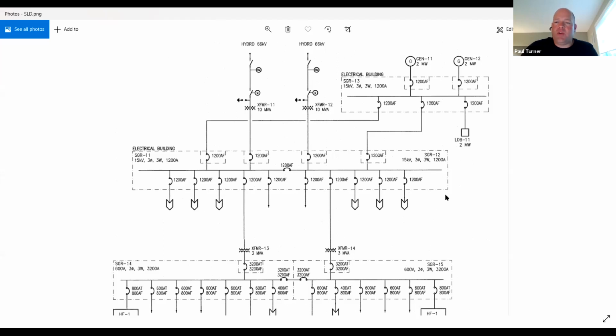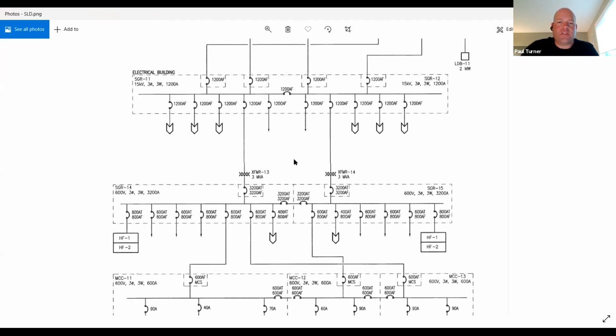You typically have a soak period as well, maybe not quite as long as 12 hours or 24 hours, but maybe 2 or 3 hours to confirm that there's no hotspots within the switchgear. Measure voltage, measure current, make sure there's no hotspots in the equipment, then proceed with energizing the downstream electrical systems. That would include closing the breakers in the switchgear to provide 15 kV power to transformer 13 and transformer 14. These step-down transformers step the 15 kV feed down to 600 volts to energize the 600 volt bus in switchgear 14 and switchgear 15.